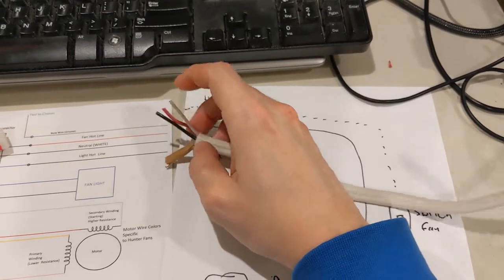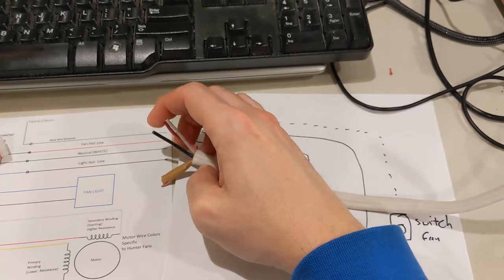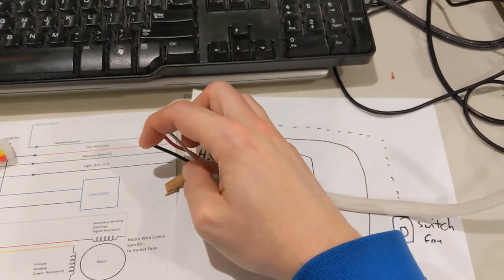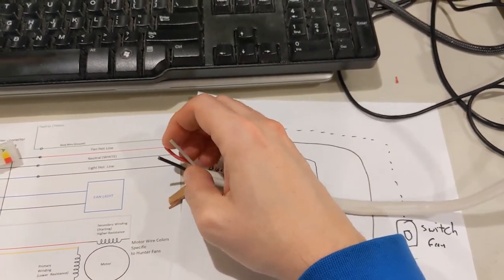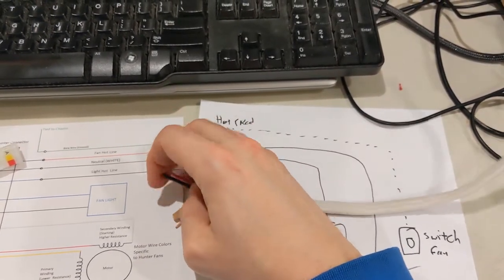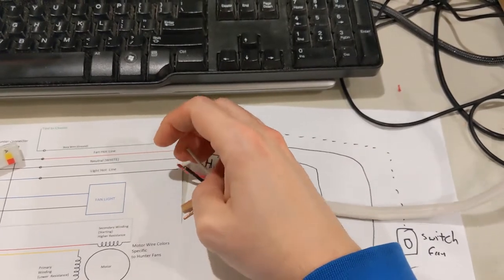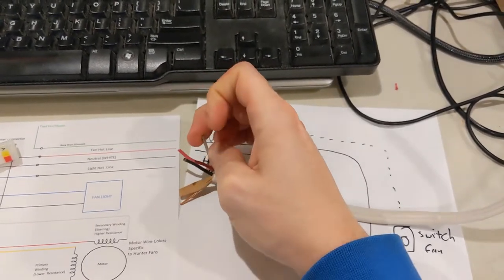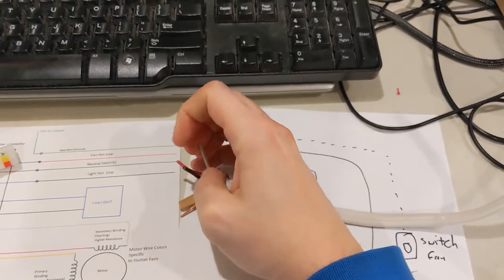This one is the safety ground. For this particular setup, you're going to need at least one hot per each thing you're controlling. The motor is going to need one hot, the light is going to need one hot. Typically black is primary, red is secondary. And then the neutral is going to be the return - so you have a neutral that's common to them. But this has to be wired from the wall to here correctly, otherwise it's not going to work.